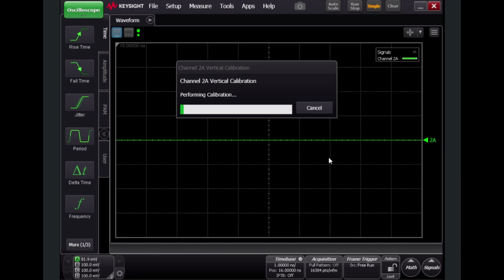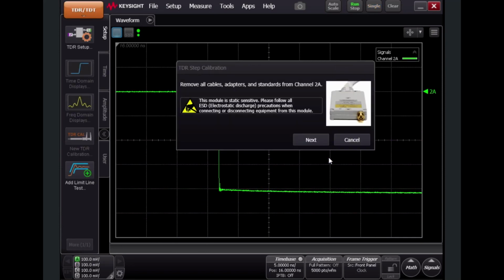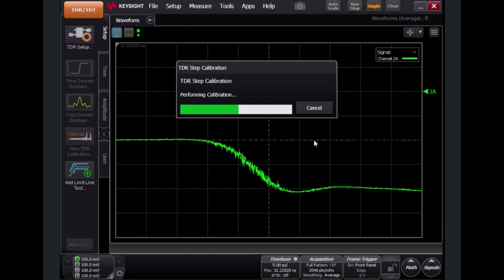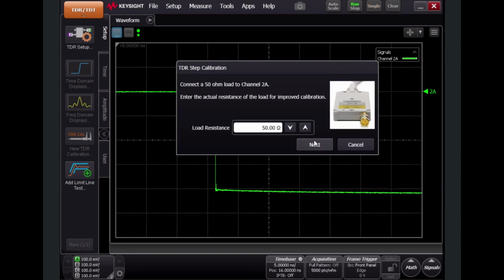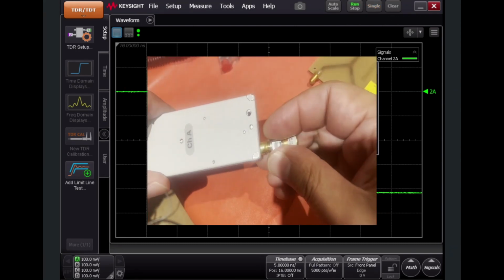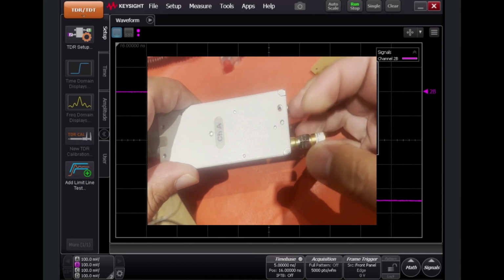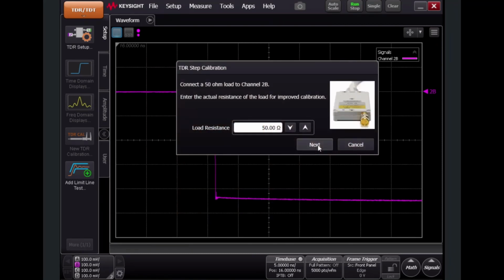The calibration is doing a vertical cal, and it will go fairly quickly. So we'll let that run. Okay, remove all cables, adapters, and standards from channel 2A. I've already done that. I'm not using these loads in my particular measurement. So we're open again. Again, this is a quick process. Connect a 50 ohm load to 2A. So I'm going to go do that. All right, and do that again. I will connect a 50 ohm load to B.